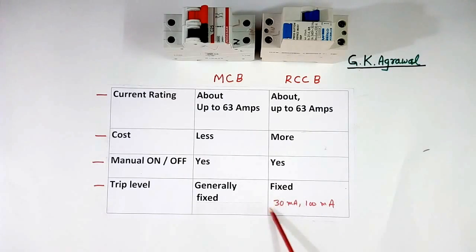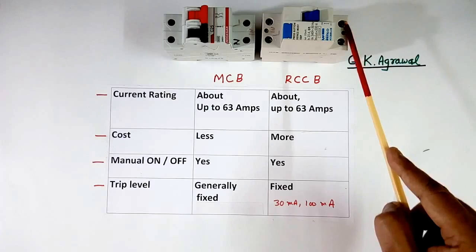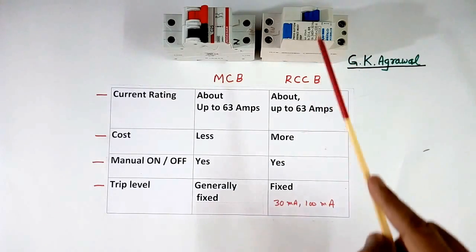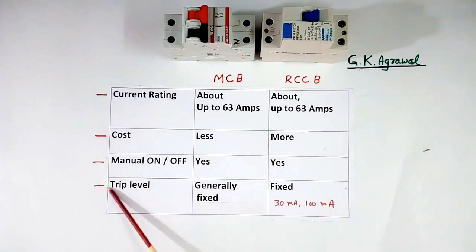This means when current difference between line and neutral becomes more than 30 mA because of earth fault, then this RCCB will trip. But in this case, trip level is defined based on the load current.